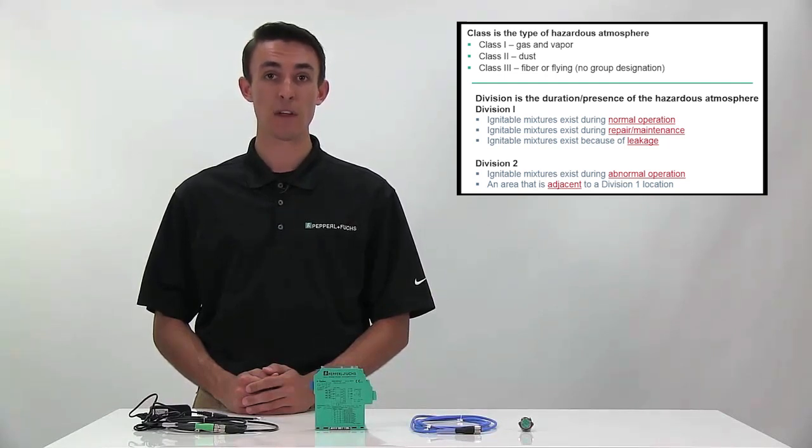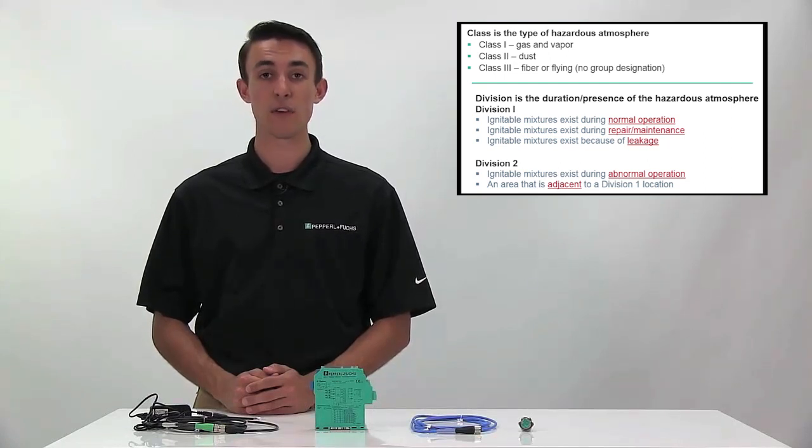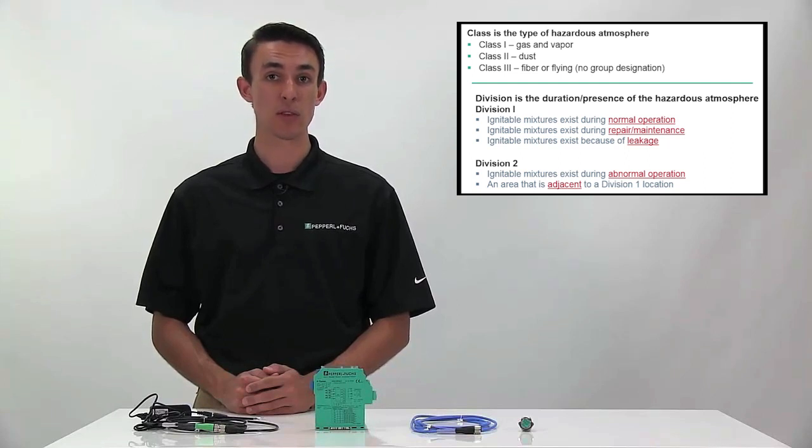Inductive sensors typically have either a 2-wire DC or a 2-wire DC NAMUR output and it is very important to denote the difference between the two. 2-wire DC NAMUR output inductive sensors are used in hazardous environments due to their low current and low voltage operating systems.